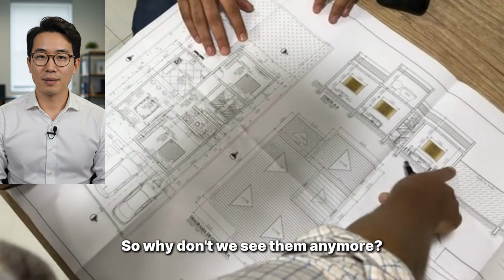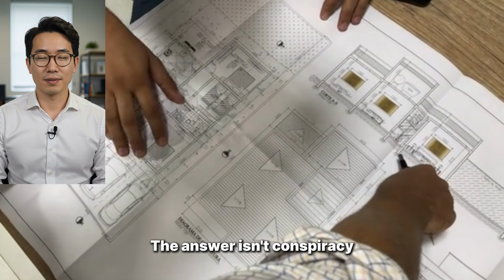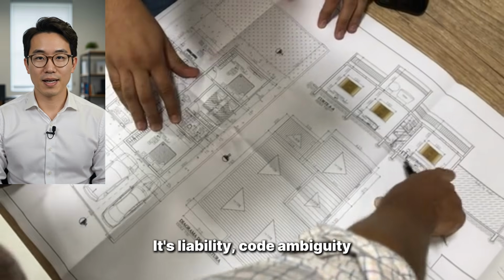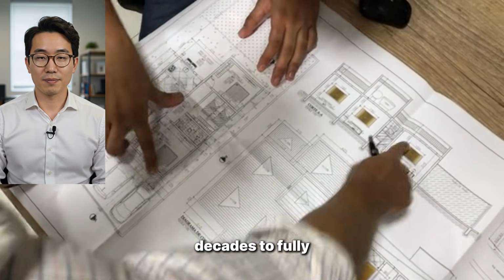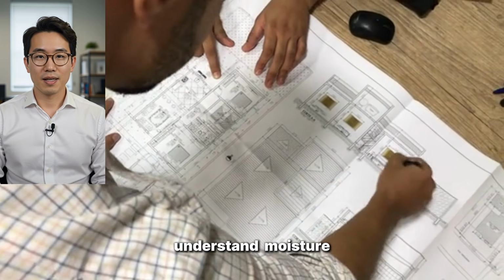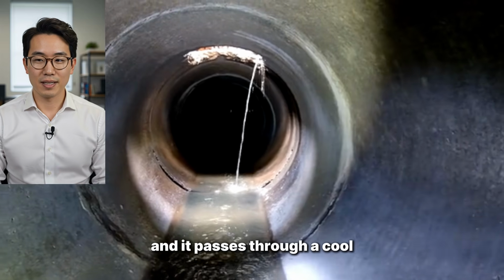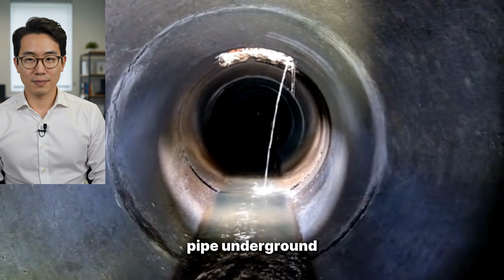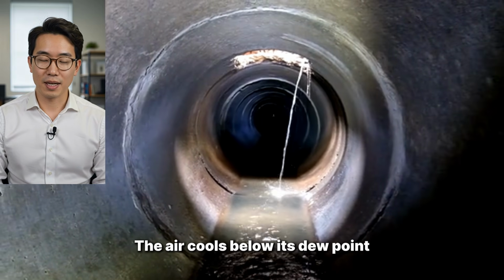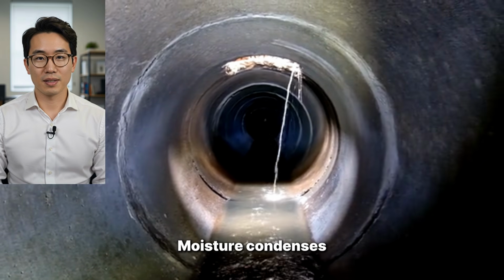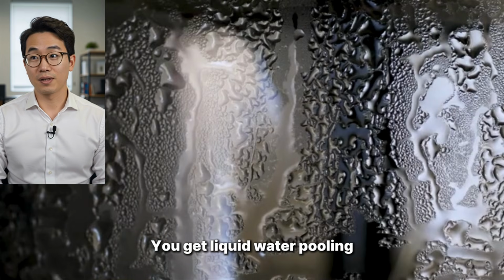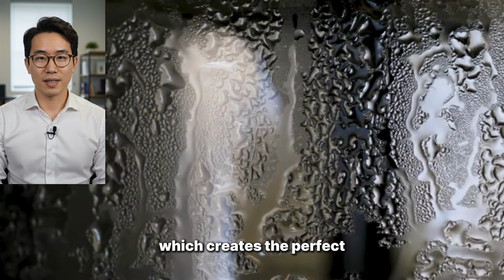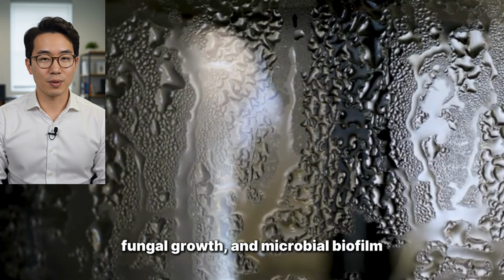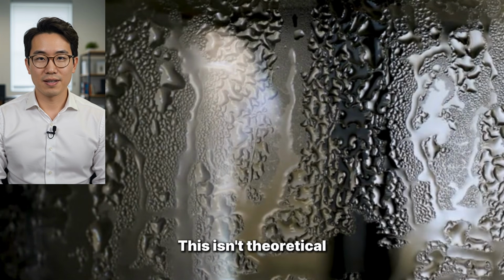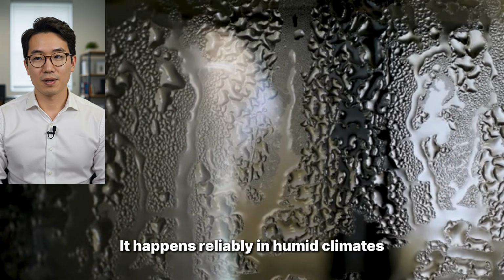So why don't we see them anymore? The answer isn't conspiracy. It's liability, code ambiguity, and a problem that took engineers decades to fully understand. Moisture. When outside air is warm and humid and it passes through a cool pipe underground, something inevitable happens. The air cools below its dew point, and moisture condenses. You get liquid water pooling inside the pipe, which creates the perfect environment for mold, fungal growth, and microbial biofilm. This isn't theoretical. It happens reliably in humid climates.